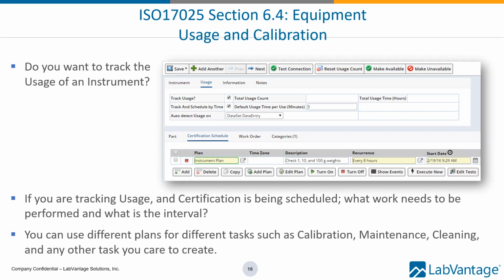Also, if you note at the top of the image where it says test connection, that would be used to test the connection to the piece of equipment if you've decided to interface that equipment and capture the readings directly from it into the LIMS rather than a person needing to type those values. Also important to note are the two buttons on the far right that make available or make unavailable the piece of equipment. This is important, as mentioned earlier, so that if an instrument does not pass its specifications, it can be taken offline, corrected, and then brought back online.